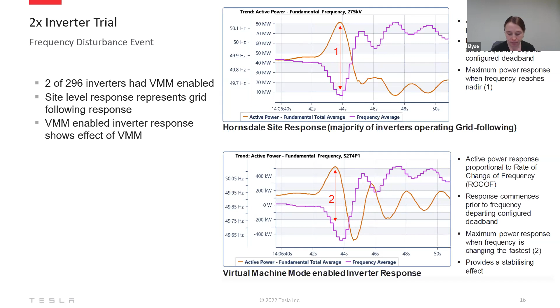The lower graph is taken from a meter at the inverter terminals of one of the machine mode enabled inverters. With this one, you can see the response is different, where the peak in active power corresponds to the highest rate of change of frequency. So you can see that inverter injects power during the decline of frequency to help raise the frequency nadir, or the minimum frequency, and provide stabilization to support recovery prior to the frequency departing the deadband. So much quicker response than your traditional frequency watt response. So this is evidence of the grid stabilizing features in action.